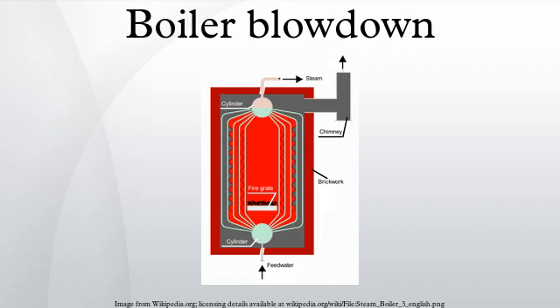Several short blowdown events remove sludge more effectively than a single continuous blowdown. Shorter blowdown events cause less significant changes in boiler water level and are safer during periods of high steam demand.